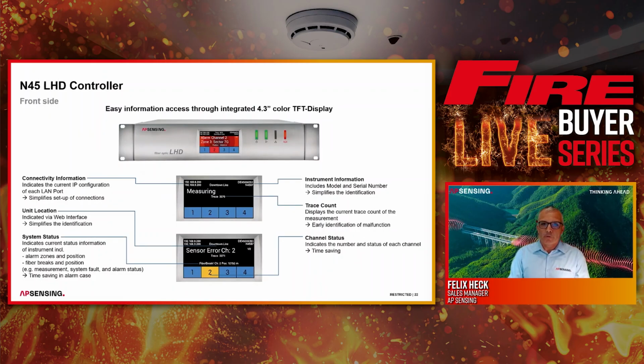On the front, as you can see here, we have a color TFT display with all the information that you might need during the operation. Alarms, faults, measuring status of the controller. And that is a very good feature that we integrated here: the installers can also program their address and their information in this screen. And if there's an annual maintenance coming up, the display will then show, please contact company XY to do the annual maintenance.